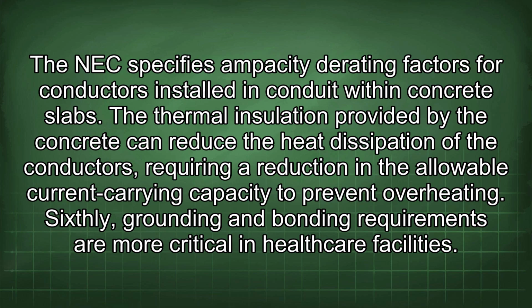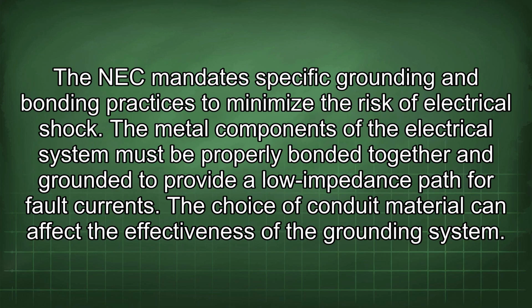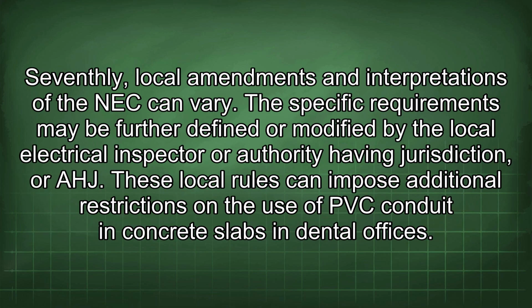Sixthly, grounding and bonding requirements are more critical in healthcare facilities. The NEC mandates specific grounding and bonding practices to minimize the risk of electrical shock. The metal components of the electrical system must be properly bonded together and grounded to provide a low impedance path for fault currents. The choice of conduit material can affect the effectiveness of the grounding system. Seventhly, local amendments and interpretations of the NEC can vary. The specific requirements may be further defined or modified by the local electrical inspector or authority having jurisdiction, or AHJ. These local rules can impose additional restrictions on the use of PVC conduit in concrete slabs in dental offices.